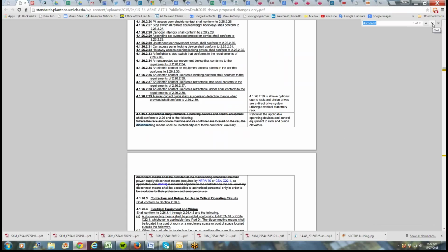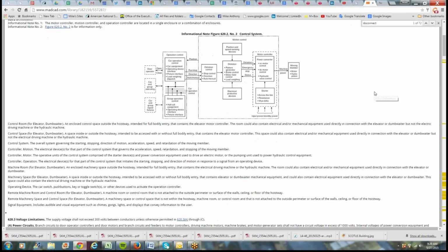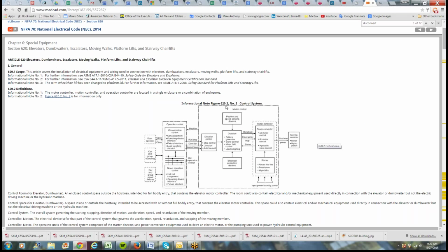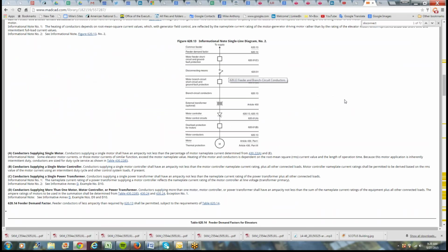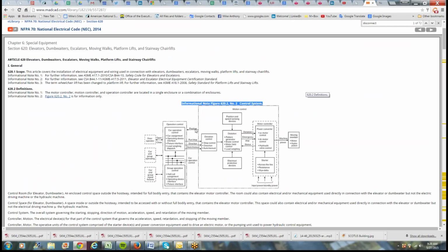the manufacturer has a disconnect in there so that you can kill power to the controller. Now you have to have one outside the hoistway that's feeding power to it, but the elevator journeyperson that's working on it has to know where it's at, and it's got to be in close proximity so that he can shut it off to prevent an injury. Okay, I see. So we're looking at 4 disconnects by the time we're done. Mm-hmm. We don't need the one in the controller if the one on the landing is in close proximity.